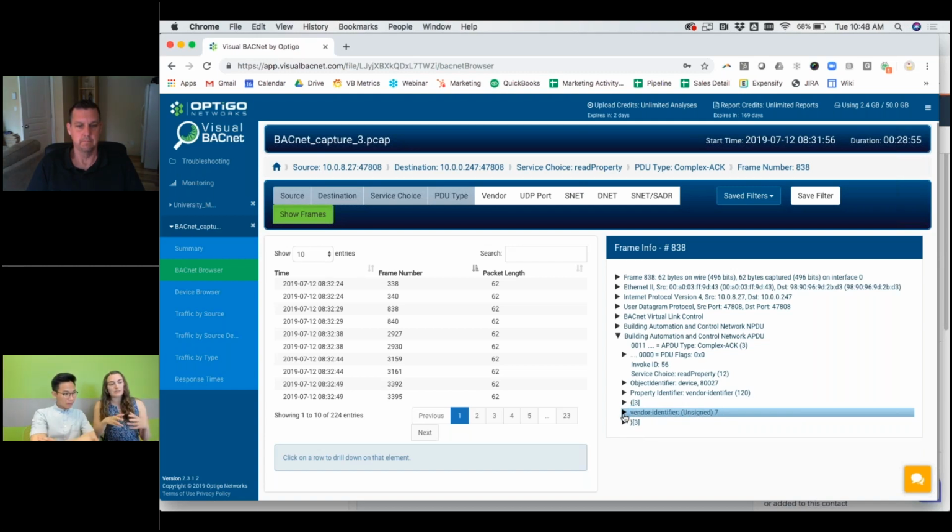Every single vendor out there has a number associated. When you scroll over something in Visual BACnet, you'll see it pop up and it will say Siemens or Logic, whoever it is. We've just cross-referenced and said, okay, we know 7 is Siemens, therefore we'll put the information in. The 7 represents that information. So the fact that it responded a lot of times and was still requesting it is a bit problematic. It can be improved.